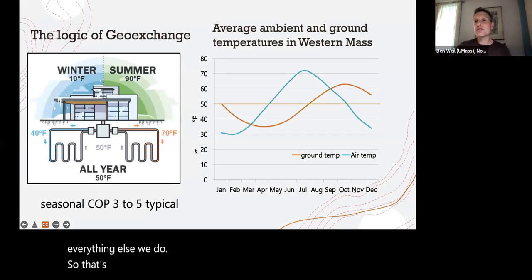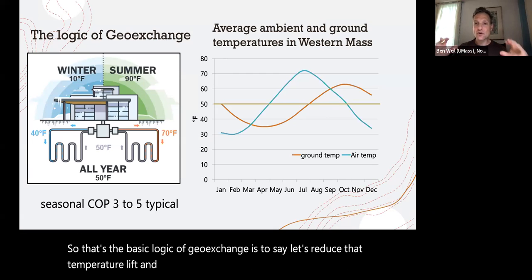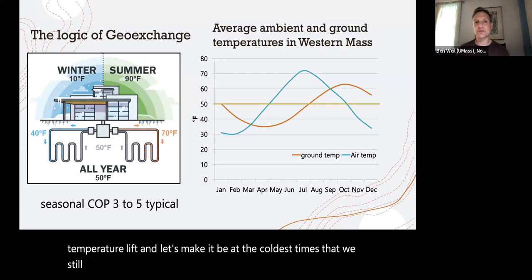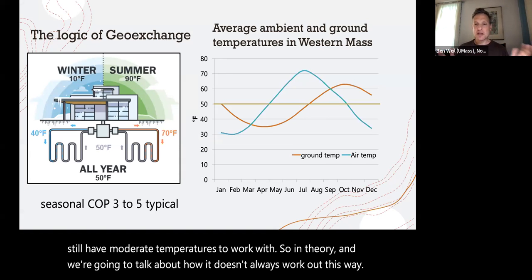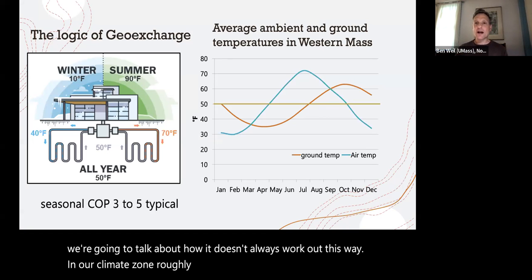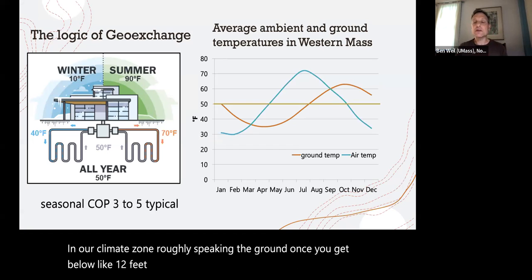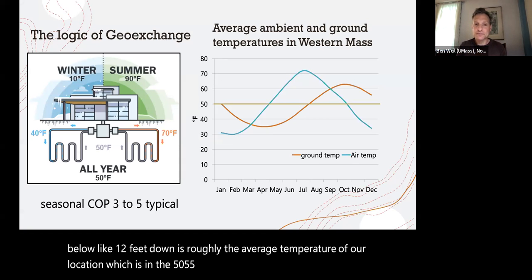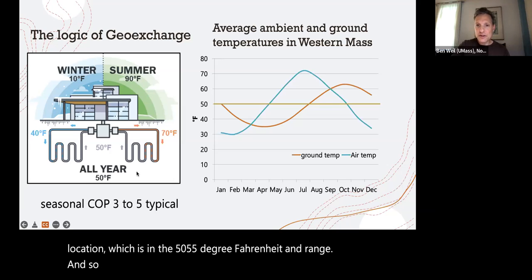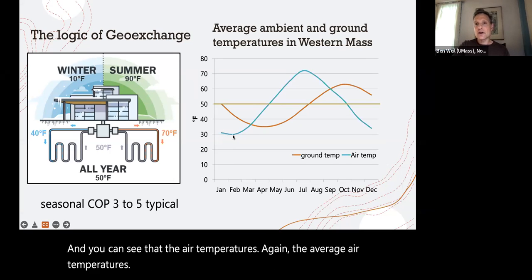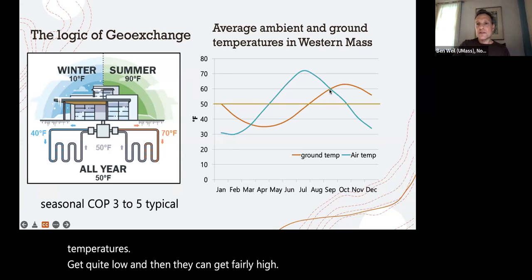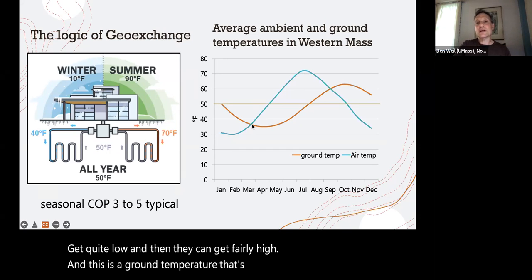So that's the basic logic of geoexchange: let's reduce that temperature lift, and let's do it at the coldest times, when we still have moderate temperatures to work with. So in theory, and we're going to talk about how it doesn't always work out this way, in our climate zone, roughly speaking, the ground, once you get below about 12 feet down, is roughly the average temperature of our location, in the 50 to 55 degree Fahrenheit range. And that's represented by this line running across here. And you can see that the average air temperatures get quite low, and then they can get fairly high. And this is a ground temperature about 6 feet down.